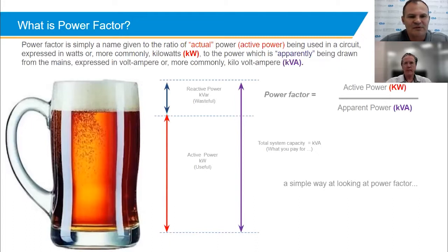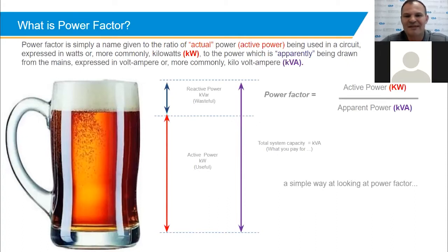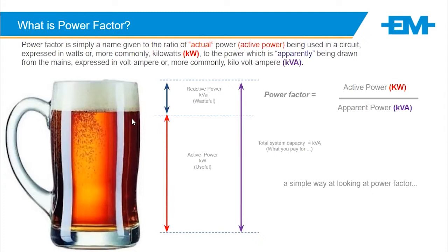Okay, so where do we start? What is power factor? It's simply a ratio of actual power being used by your circuit, being your internal grid, and normally you will see that as kilowatt, to the power which is apparently being drawn, which is then displayed as what we call kVA. So everyone uses, let's call it, the beer analogy. If you have a beer, the useful part, which we refer to as active power here, is the kilowatt. It's the good part, and then the waste would be the foam, and that's what we're referring to as reactive power. On most grids, from the utilities, they will charge you for kilowatt and kVA. So you will pay for what we call this wasteful foam.